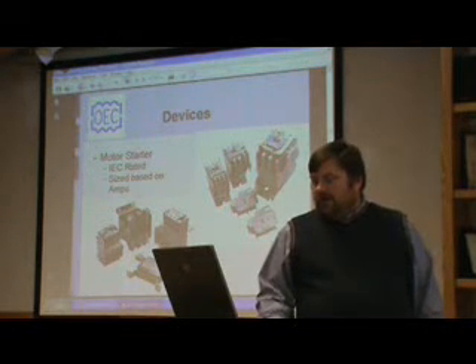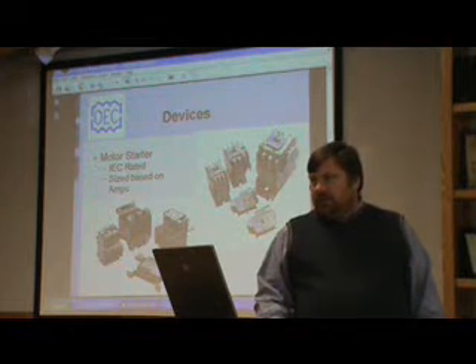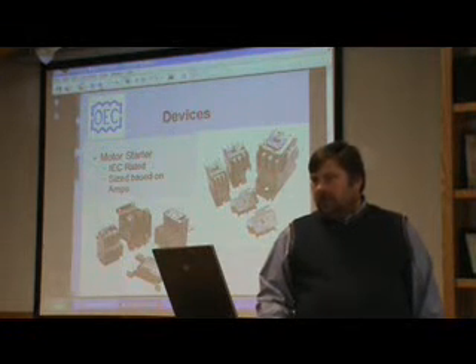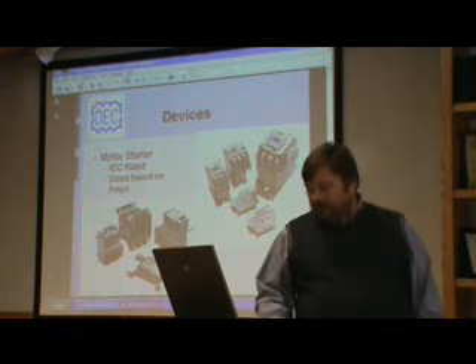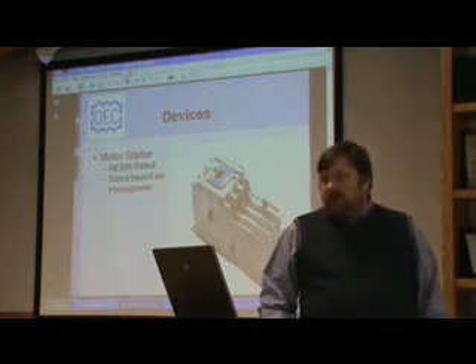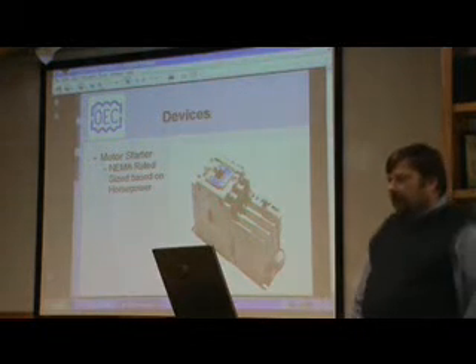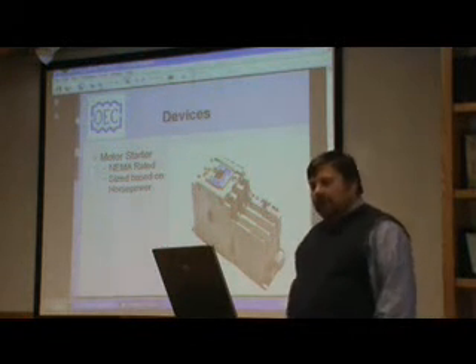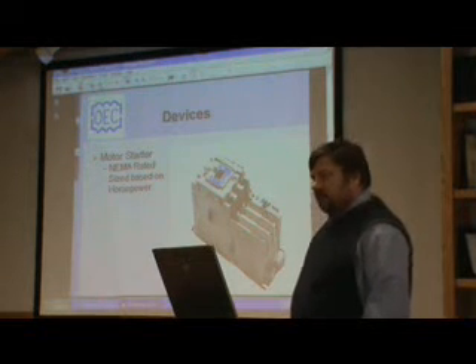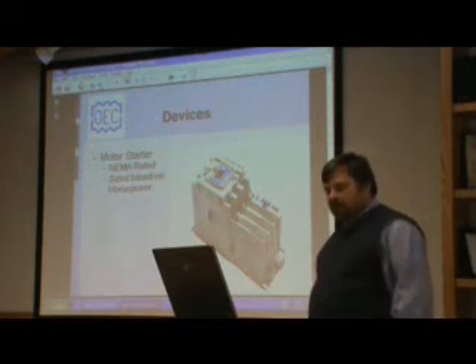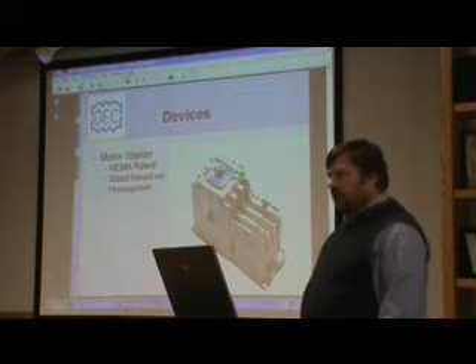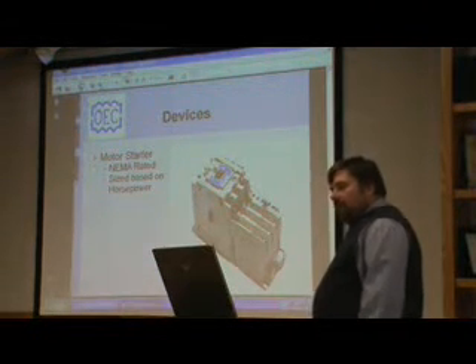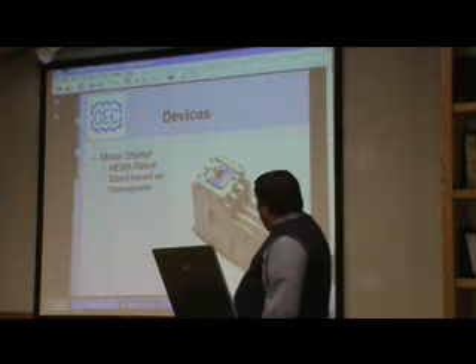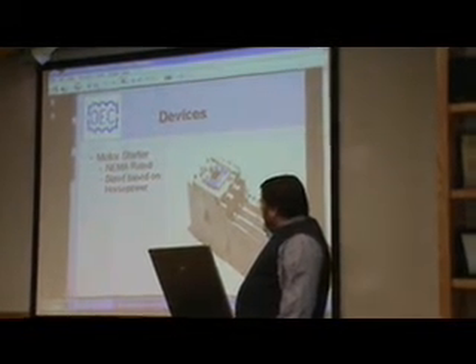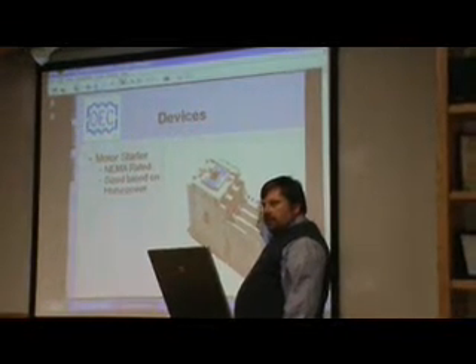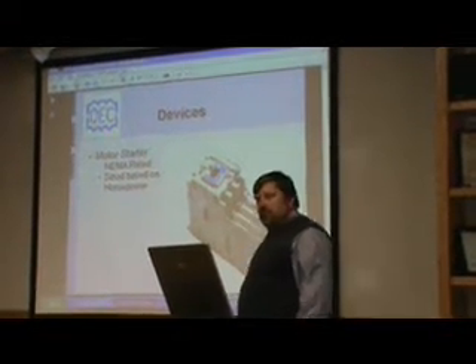The IEC rated devices are rated based on the current that they can handle. So they'll have a 12 amp or 18 amp or some amperage rating that they're designed for. The next starter device we talk about is the NEMA rated starter. I'm sure everybody's heard NEMA before. NEMA stands for National Electrical Manufacturers Association. That's the United States-based organization that sets the standards for electrical power. The thing to know about the NEMA starters is most of them still have these replaceable packs, but they've switched so that the little device you stick in there actually has an adjustment rating on it. So you can adjust the ratings on those heater packs.